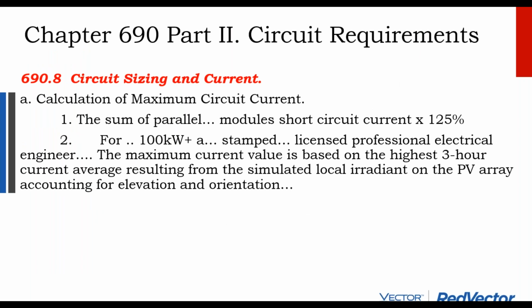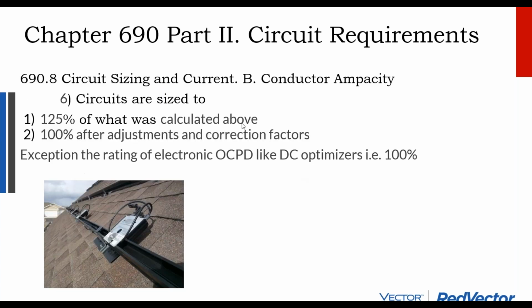And so here, when we're calculating solar module circuitry, we take all of the amperage of the modules, and then we add 25% to it as an additional safety factor. Whereas an engineer can look at that day of maximum production expected and not use the extra 25% allowance. And so then we get into the circuit sizing.